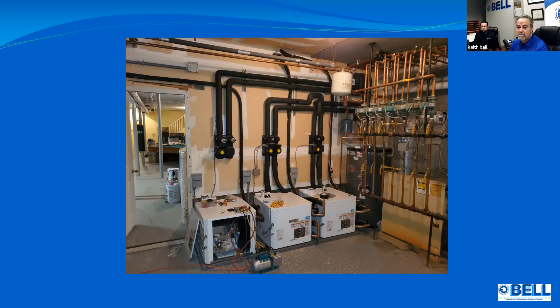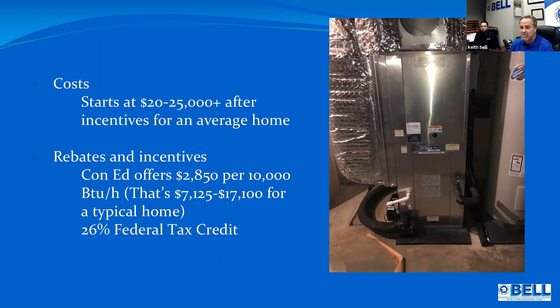So a standard geothermal unit, if you have say a 2 or 3 ton furnace in your basement and you want to take that out and put it back in, it depends with the Con Ed incentives, and geothermal has a 26% federal tax credit. You start stacking those things on top of each other. Basically it's not that much more money than doing a really good regular system. And you now are benefiting from no fossil fuels. You're getting that 3 to 5 to 1 ratio for the next 30 years. And the fields are guaranteed for 30 years by the manufacturer, and the pipes are very sturdy. We have very, very minor issues with fields over the years. And these are the rebates. They offer $2,800 for 10,000.